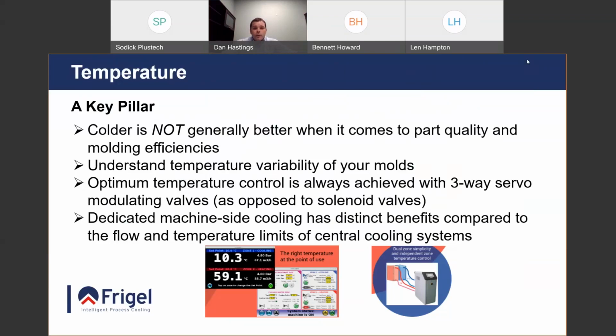Optimum temperature control is always achieved with three-way servo modulating valves. Instead of all or nothing opening and closed solenoid valves, we can get maybe a servo valve that has 0 to 100% control and can dose the system. Well, one, you get better approaches from the cooling water system, and two, you're able to achieve better temperature control deviations. So maybe instead of plus or minus 2 or 3 degrees from the set point, maybe we can get plus or minus 1, which is going to benefit your mold and your repeatability without a doubt.